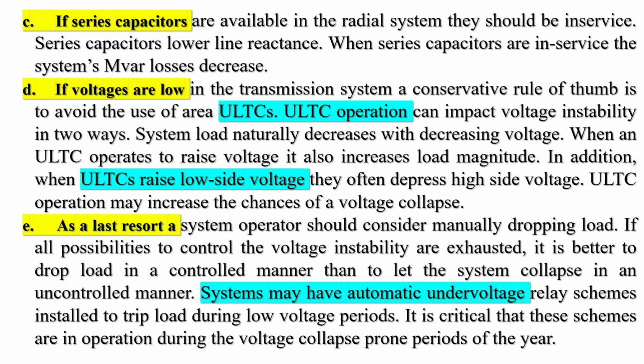If voltages are low in the transmission system, a conservative rule of thumb is to avoid the use of area ULTCs. ULTC operation can impact voltage instability in two ways. System load naturally decreases with decreasing voltage. When a ULTC operates to raise voltage, it also increases load magnitude. In addition, when ULTCs raise low side voltage, they often depress high side voltage. ULTC operation may increase the chances of a voltage collapse.